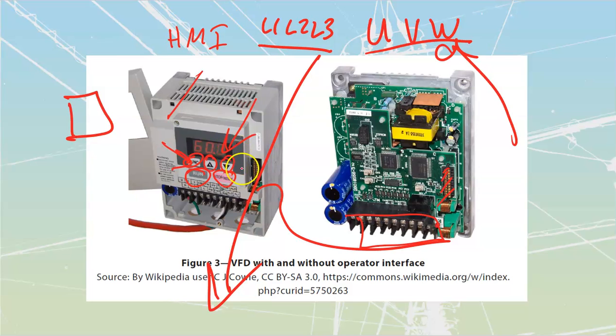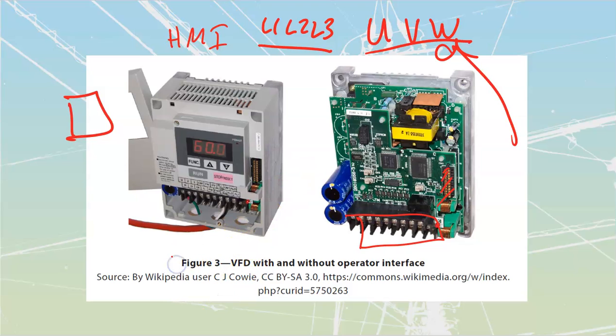But it'll be the same: if I've got a whole pile of these that I'm going to put together for a ventilation system, I can program one of these, and then store it onto that card, pull that card out, carry it to the next VFD, just drop it in, save it to that one, then carry it out, take it to the next one, drop it in, save that one, etc. And so it allows you to do a lot of programming relatively quickly, particularly if you're doing built-from-scratch type systems. If you're putting together systems for pumps, and you're always shipping out the same system, you program them all the same, it's a really fast way of doing that.